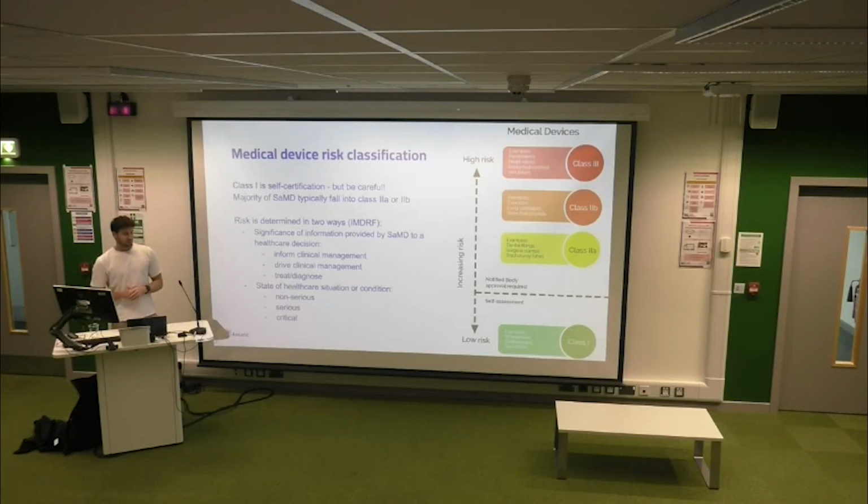But the robustness of those devices can vary. What we're seeing in Europe is that, some would argue, every single software as a medical device would be class 2A or above, although some people argue the difference. The UK MDR is going to align more closely with the EU MDR, and therefore there's a chance that all current class 1 devices might be upregulated to class 2A and then have to have an external conformity assessment. So just something to be aware of. Generally, most people would see most software as a medical device as class 2A or above.